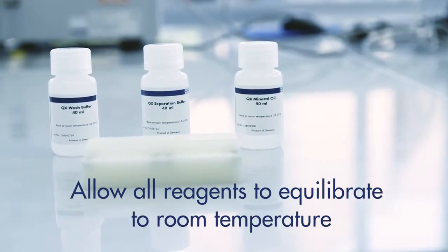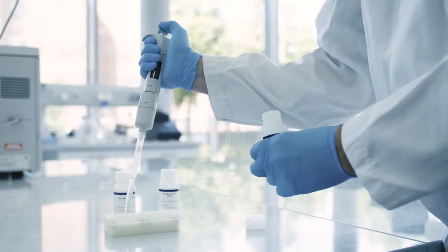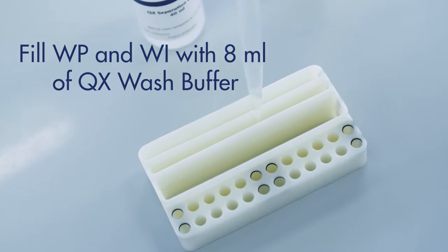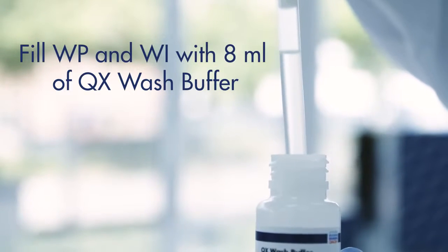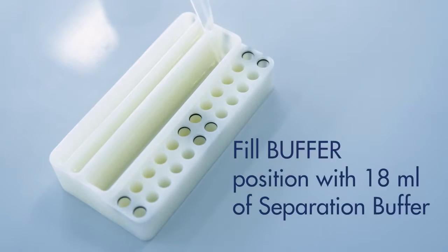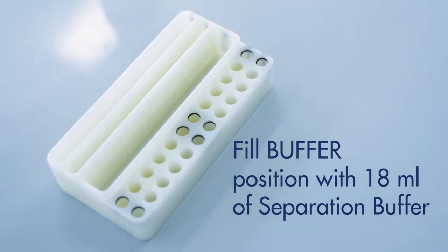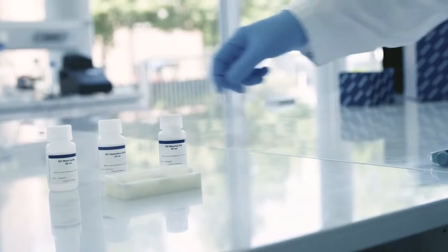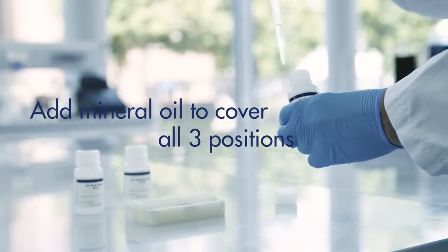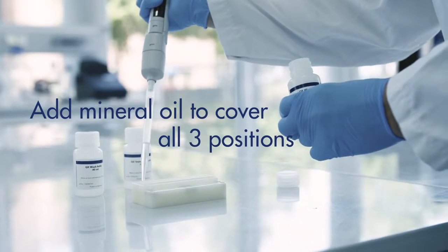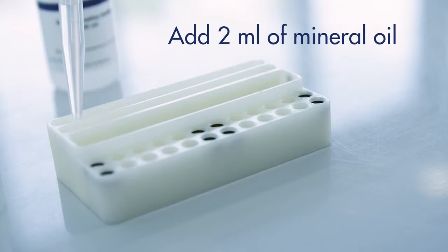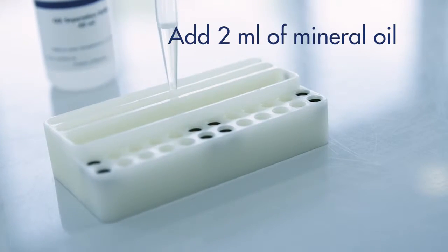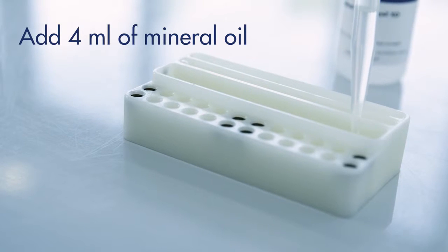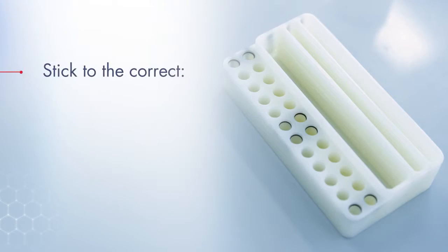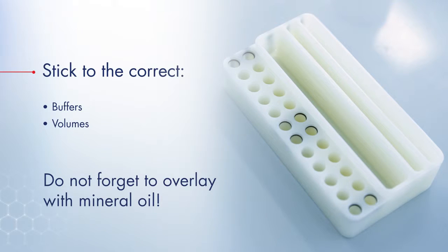Allow all reagents to equilibrate to room temperature. Fill the WP and WI positions of the buffer tray with 8 milliliters of QX wash buffer. Fill the buffer position with 18 milliliters of the appropriate separation buffer. Carefully add mineral oil to cover all 3 positions to prevent any evaporation. Add 2 milliliters of mineral oil to the positions WP and WI. Add 4 milliliters of mineral oil to the buffer position. It is crucial to stick to the correct buffers and volumes. Do not forget to overlay with mineral oil.